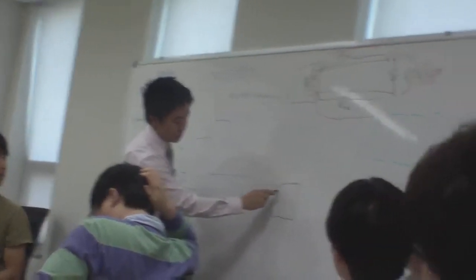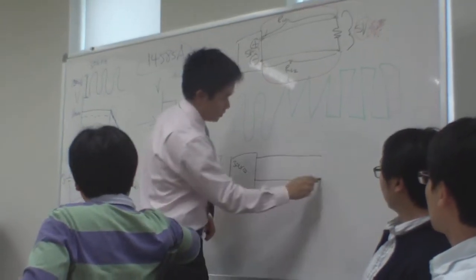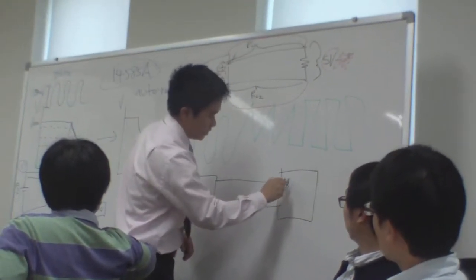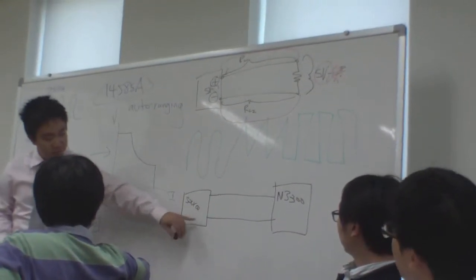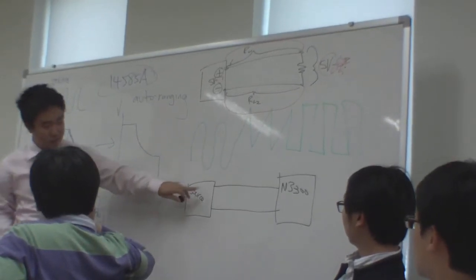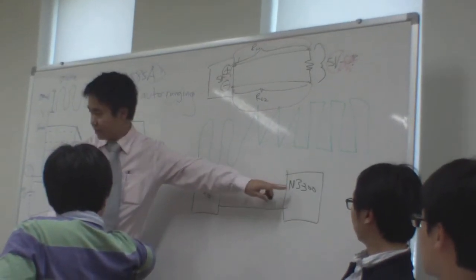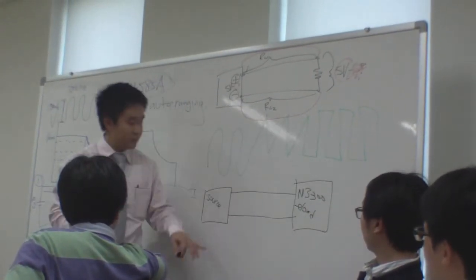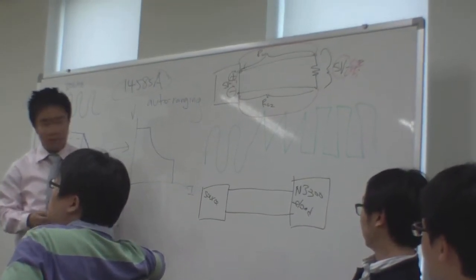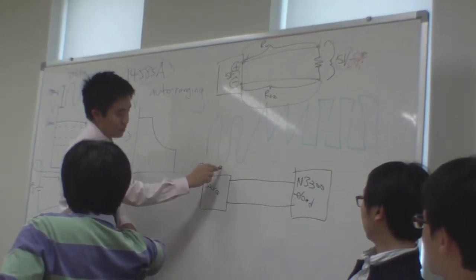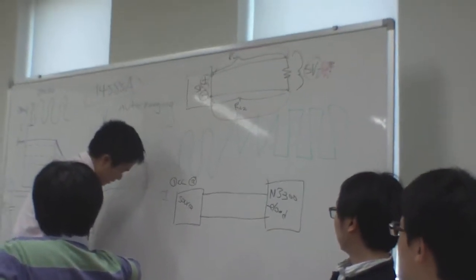So most likely you're going to have some sort of source, and that's going to be connected to the N. So this is your device under test. It's going to be a source, and you're going to connect this to the N3300 electronic load. So basically, it's very simple operation. You have 2 choices really. You have choice number 1, constant current. It's actually on the other side.